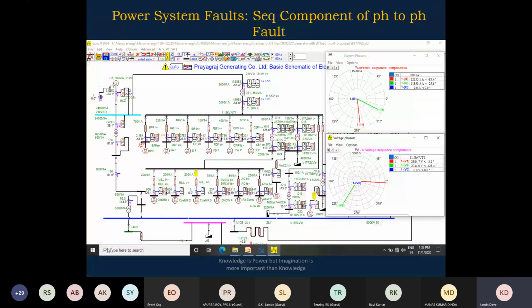Now you look at it here, it is a phase-to-phase fault. The positive sequence component is 12.1 kiloampere. The negative sequence component is 11.83 kiloampere. Fault current is 20.9, but positive sequence is 12.1 kiloampere. Negative sequence current is 11.3. Almost both are the same.